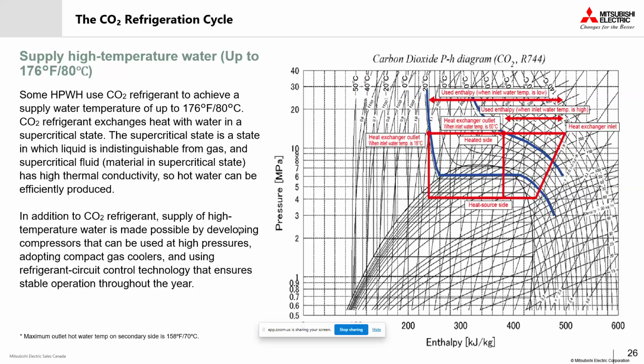That's because in this supercritical state, that CO2 refrigerant, or R744, behaves both as a liquid and a gas. This supercritical fluid has a very high thermal conductivity, and that allows the heat pump to efficiently transfer that energy to our water loop for significant temperature lifts. So that's how we achieve that high delta T that Rizwan was mentioning. Beyond just the refrigerant, modern units are designed with reliable compressors and advanced controls that can handle high pressures and adjust to changing building demands throughout the year. The end result is consistent high temperature hot water for domestic or commercial use, all while helping to reduce emissions from the building in a meaningful way.